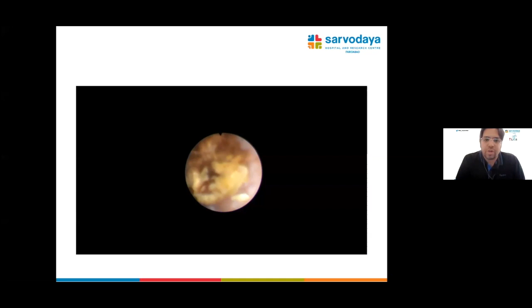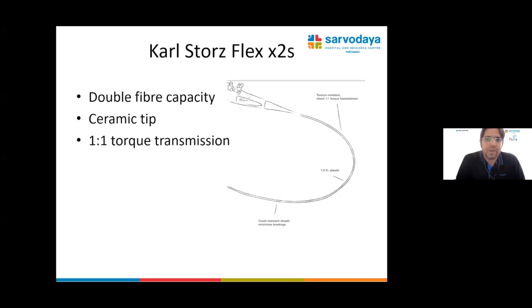So coming to the next most commonly used scope is Karl Storz FlexX 2S. It's a very nice sturdy scope with good vision. The main difference between the FlexX 2S and the earlier FlexX 2 is that it now has double fiber capacity. This gives us very good vision, because with the FlexX 2 there was an issue with the vision because of the screen door effect. And it also has a ceramic tip which protects the tip against injury from the laser fiber when we are using it. And it gives a 1:1 torque transmission.